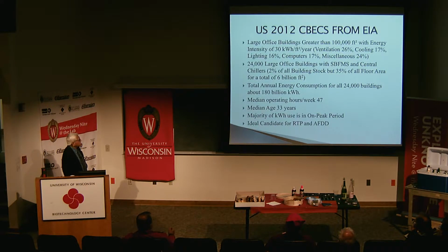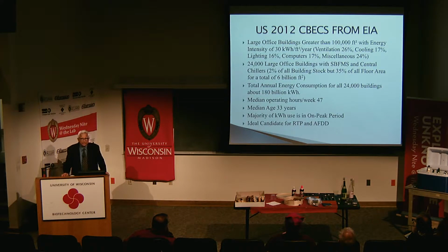Now, this is very interesting. This is the interesting data from the Energy Information Administration, EIA, for the United States 2012 survey for commercial building energy consumption survey, that's called CBECS. If you notice in this, large office buildings greater than 100,000 square feet, though they are only 2% of all building stock, they are responsible for 35% of all floor area. And they consume 30 kilowatt hours per square foot per year of energy. That roughly works out to be about 100,000 BTU per square foot per year.